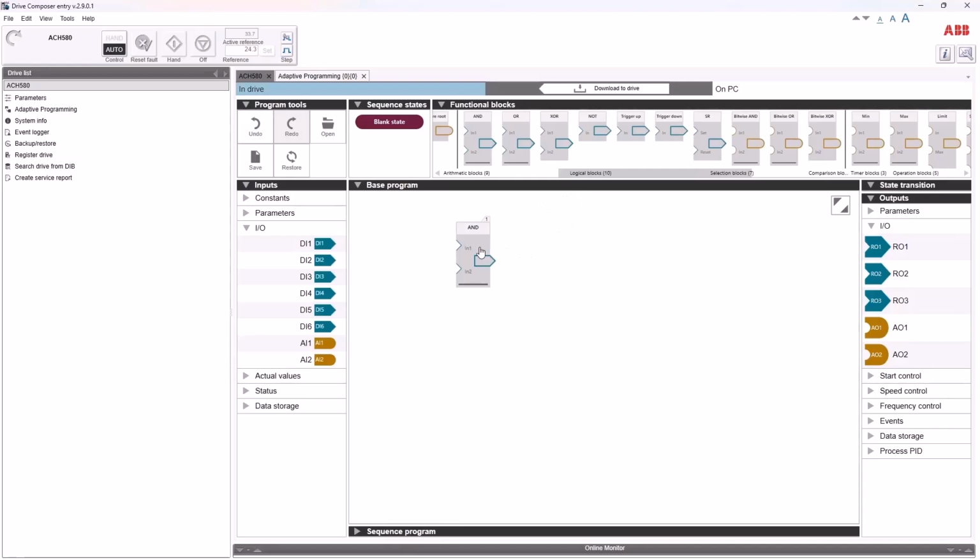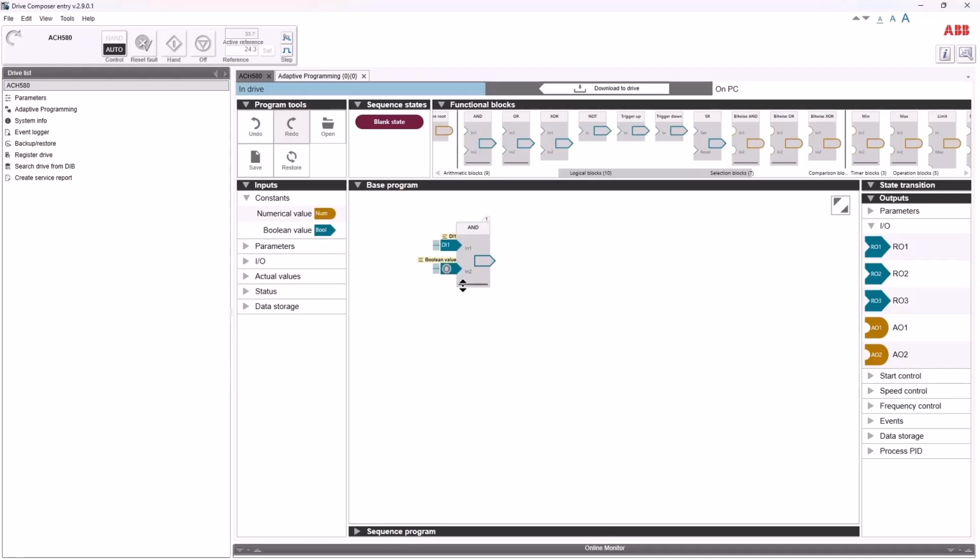The AND block can take in 2 digital inputs to start, and if you needed to compare more functions, you could have a second block where you take the state of this AND block and run it into another block to compare to something else. If you were trying to get the state of 3 AND inputs or more, the AND block has a nice feature where you can mouse over the dark gray bar on the bottom and drag it out to take up to 8 inputs. So instead of needing a separate AND block, you can just increase the number on a single block.